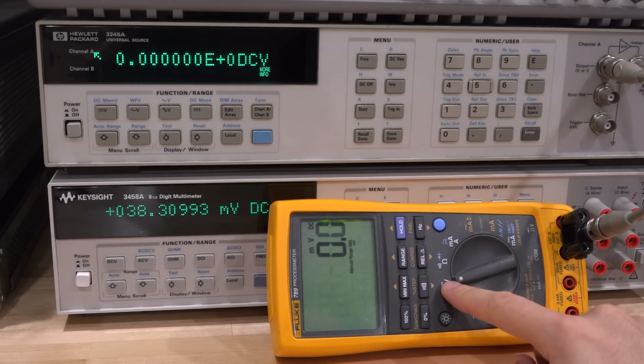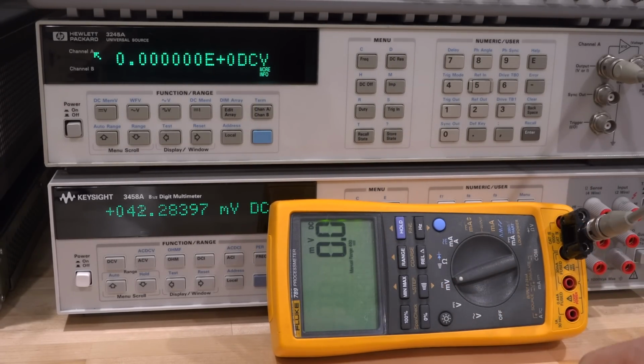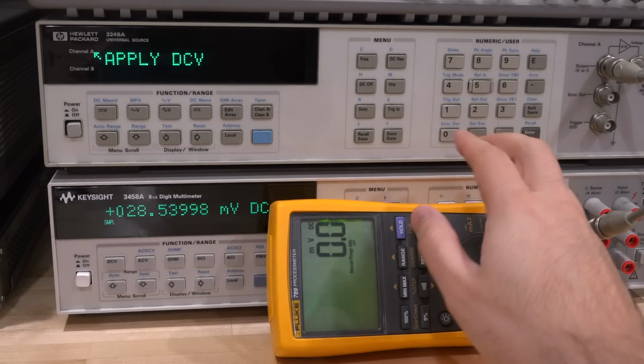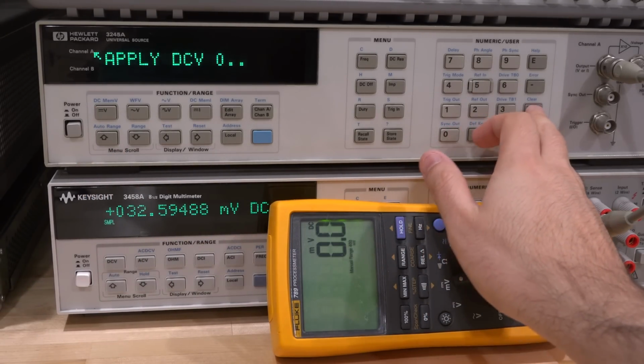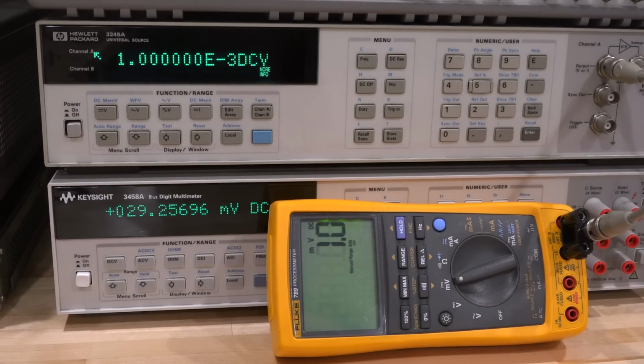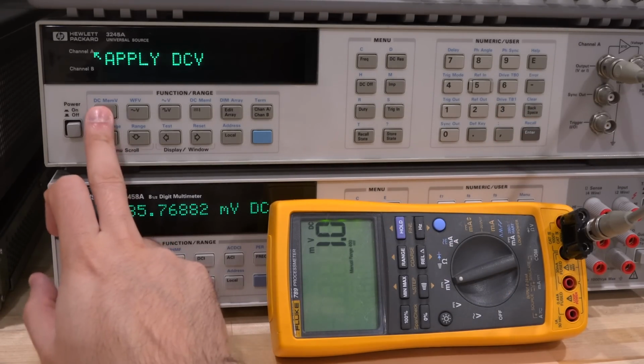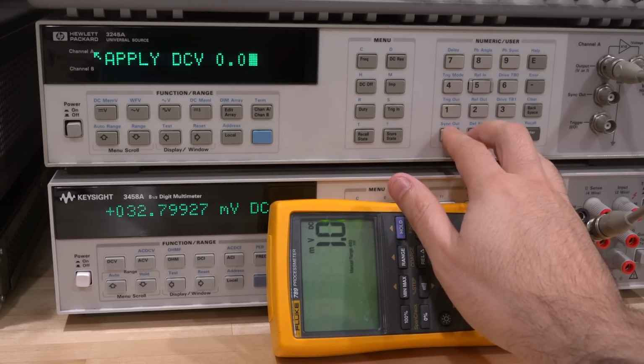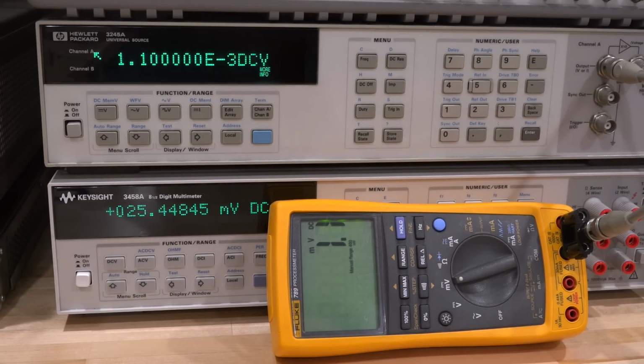So right now we're on the millivolt range, and we're directly connected to the HP3245A. So let's set that to 1 millivolt. Let's see if we get a nice 1 millivolt measurement here. Oops, that's wrong. There we go. Look at that, 1 millivolt. Perfect. We can increase it by 100 microvolt. See if it measures that difference. And it does that without any issues. So it actually works quite nicely.